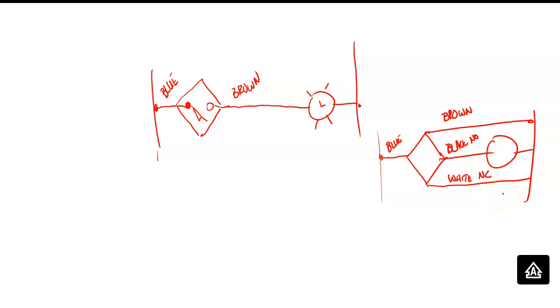On solid state sensors, that's it, guys. We have one contact, or we might have a double. It might simulate a single pole double throw, where you get a normally closed and a normally open. The white will be normally closed, and the black will be normally open. And I can show y'all some of these. We have one. Ours is a 2-wire sensor, so it's designed to work off a higher voltage, so we can afford to drop a voltage to generate the power it needs to run the electronics inside.